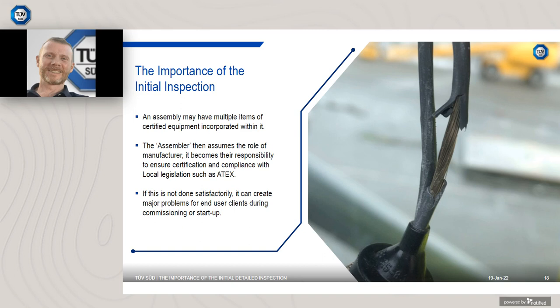A new cable was required, as not only was the inner core insulation damaged, the cable was cut too short after the gland, and no spare length was available on the cable. The user installation instructions supplied by the gland manufacturer detail correct usage.